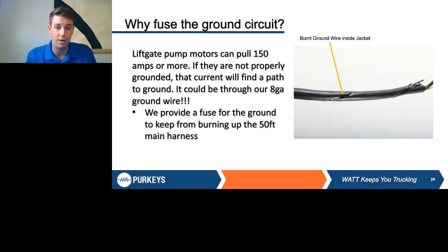So it'll search around for a ground and find our 8-gauge ground wire, which it then tries to use as its ground. But our 8-gauge wire is not designed to handle that kind of current. What happens, just like in this picture on the slide, is you can actually get melting of that wire because it gets so hot from all that power going through it.